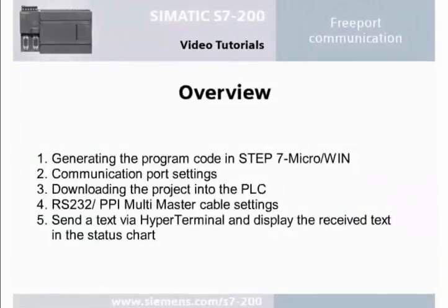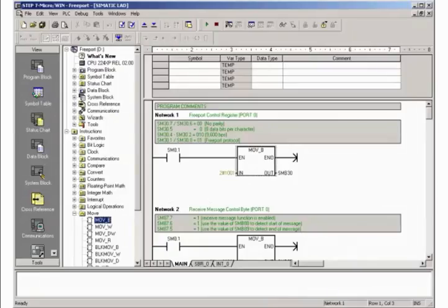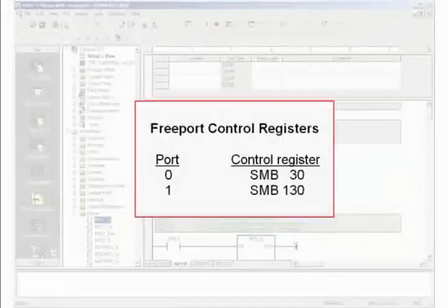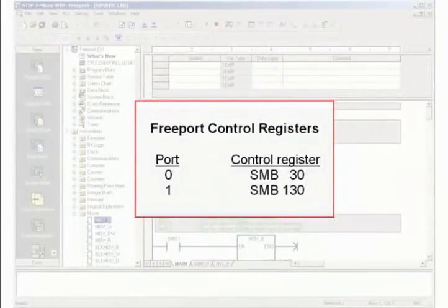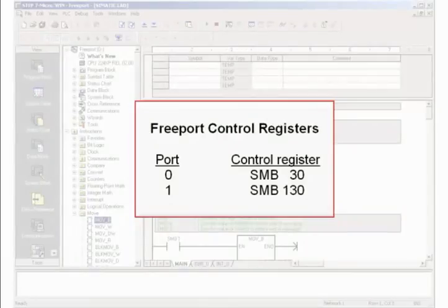The task is divided into five steps which are described below. Step 1: Generating the program code in Step 7 MICROWIN. For the free port communication, the control register SMB30 or 130 must be initialized depending on the used communication port.